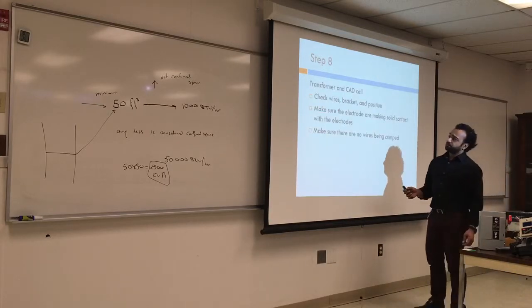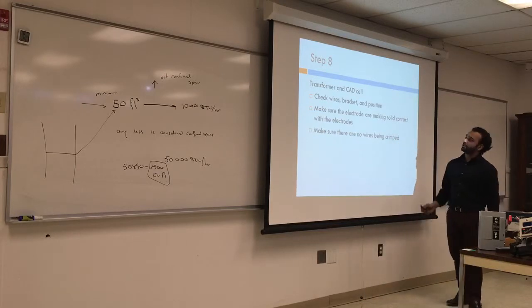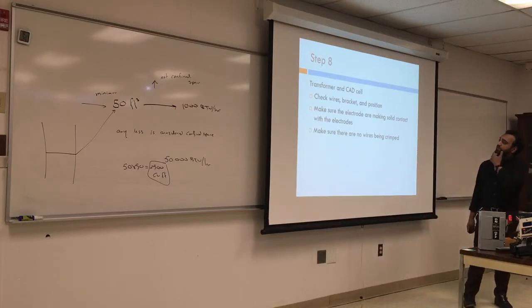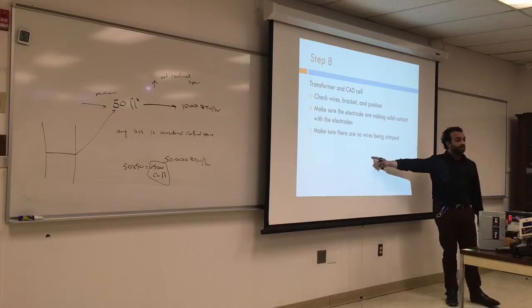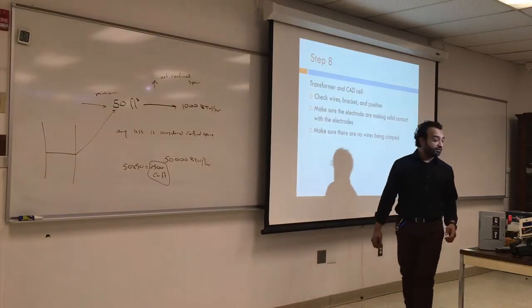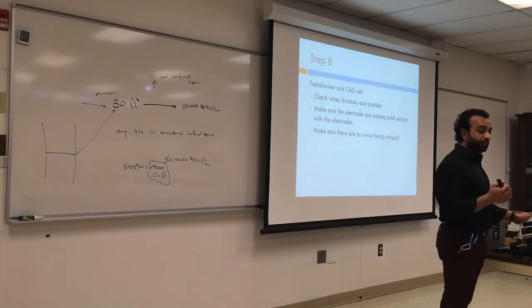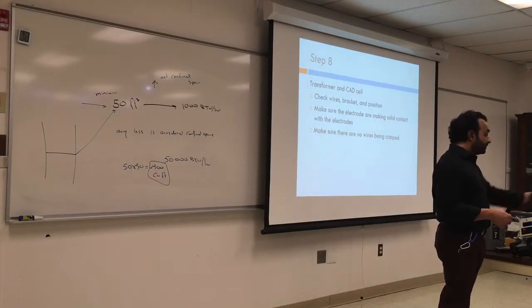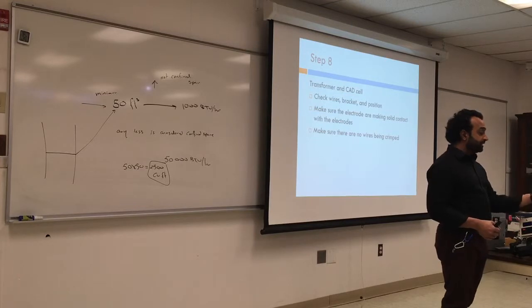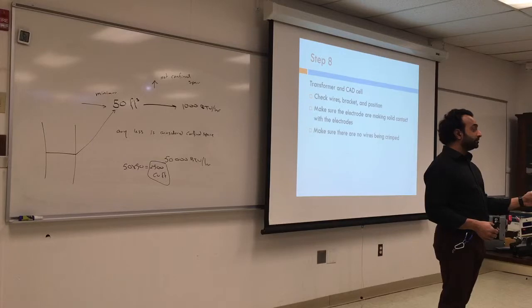Transformer and cad cell. Check the wires, brackets, and position. Make sure the electrodes are making solid contact with the electrode bus bars. Make sure there are no wires being crimped. This is very important. A lot of the time we crimp the wire in the wrong place, or we pull wires when we put it back, so be careful. Those sleeve connections get loose. If they're loose, what do you do? How do you fix this one if it's loose? It's not gripping.